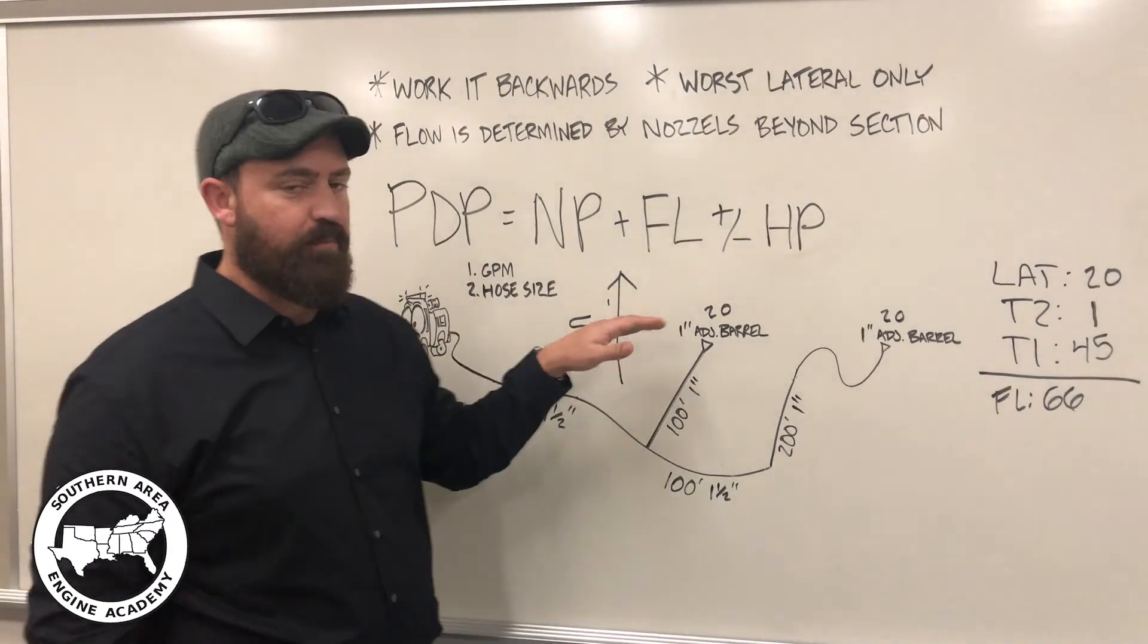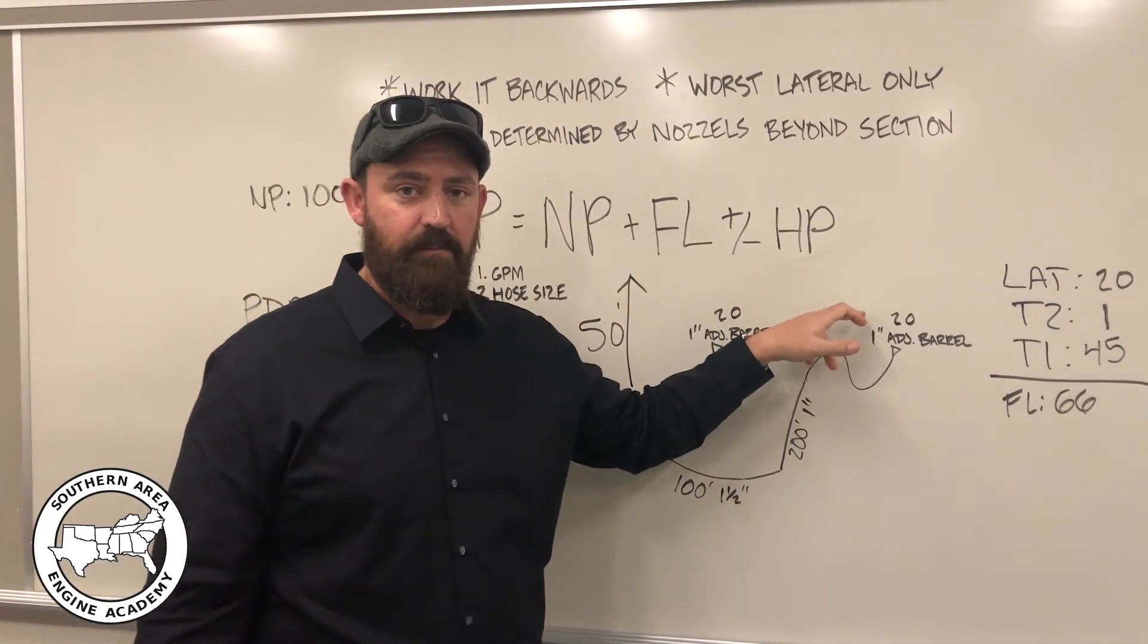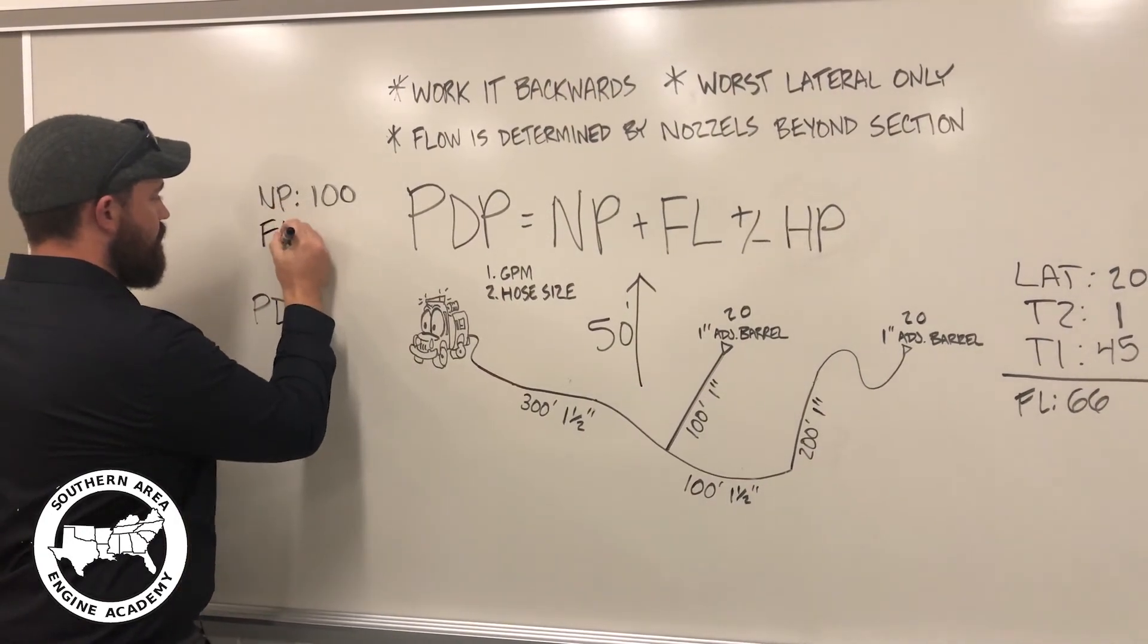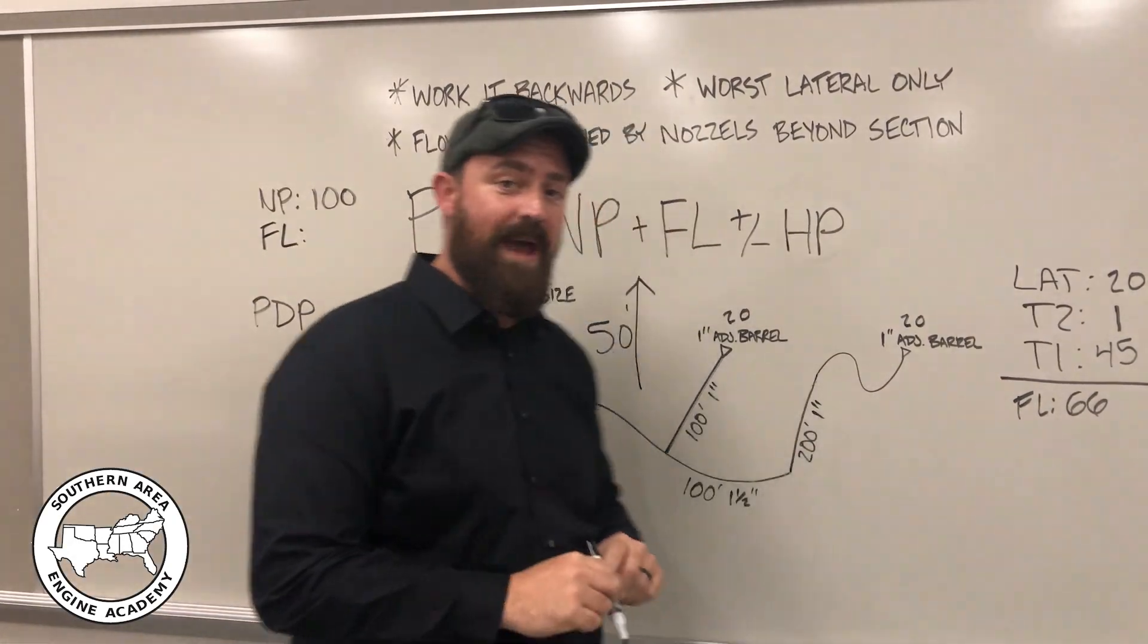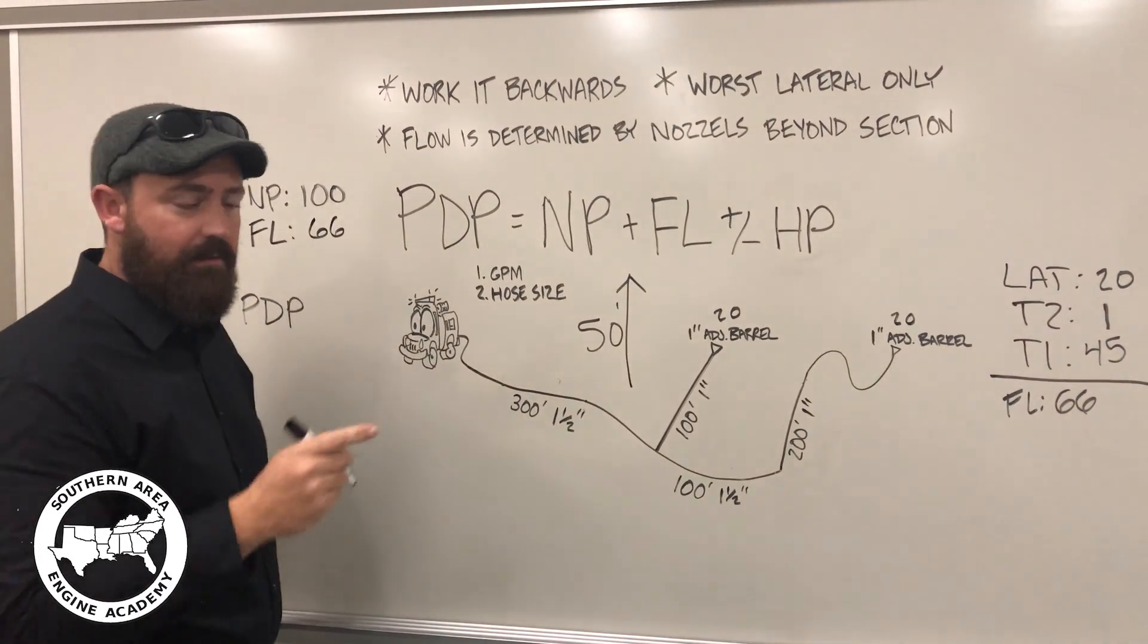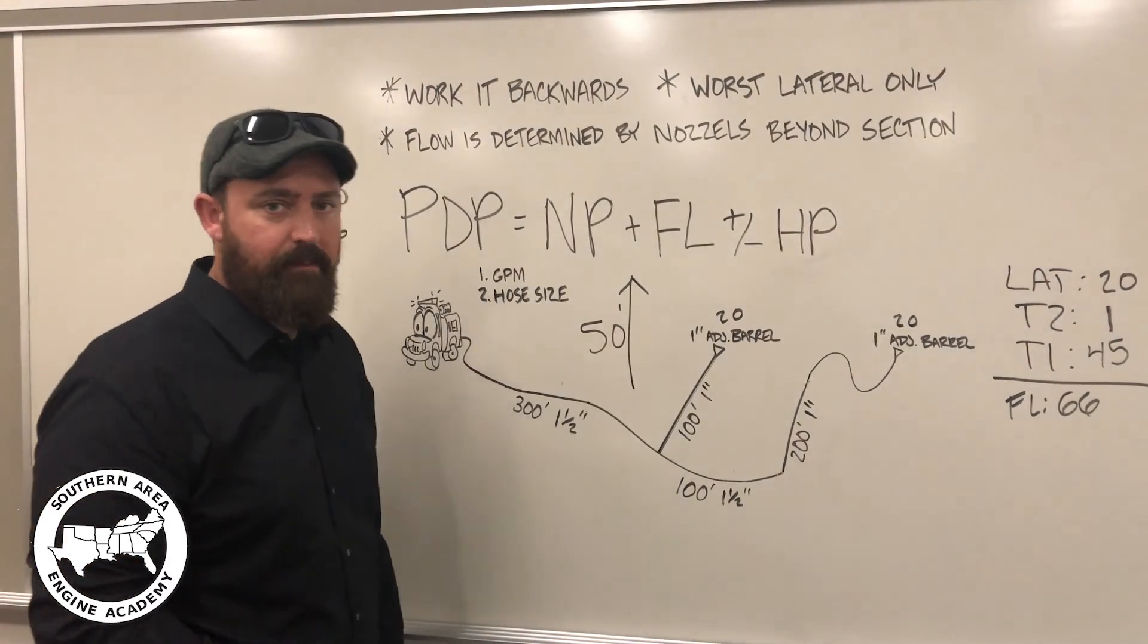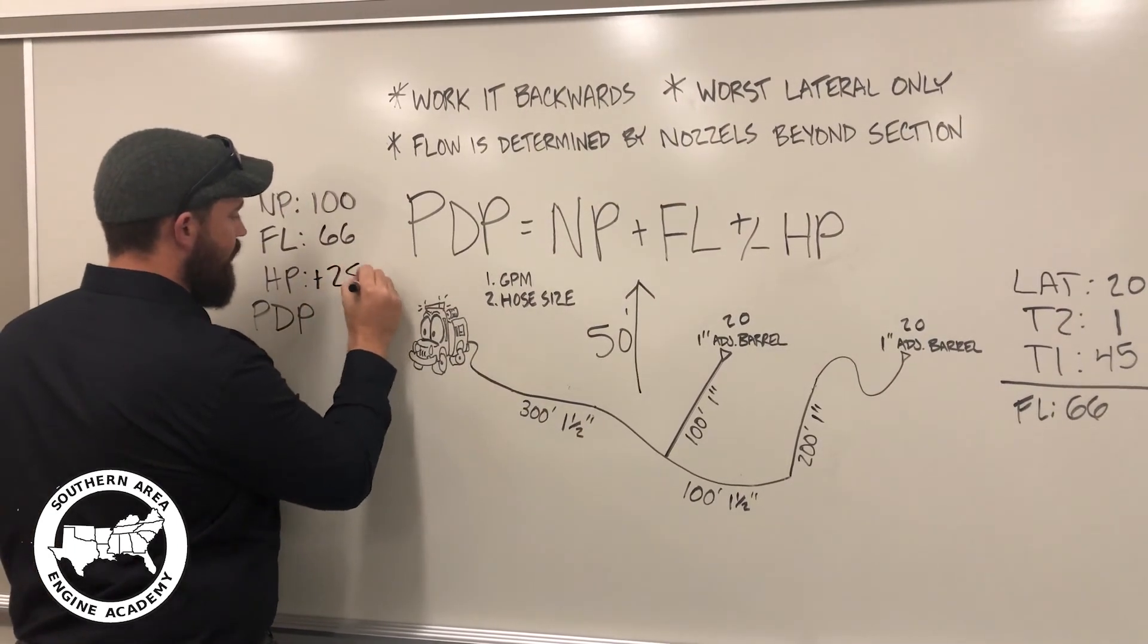So, the next portion is friction loss. We determined the friction loss for the hose lay was 66 pounds, 66 psi pressure. The last component, HP, head pressure. We determined with 50 foot uphill that we needed to add an extra 25 pounds of pressure. So, we're going to add 25 pounds.